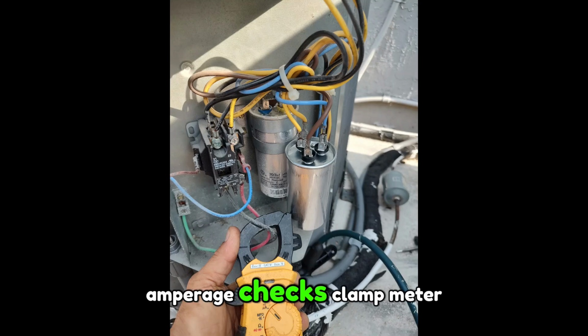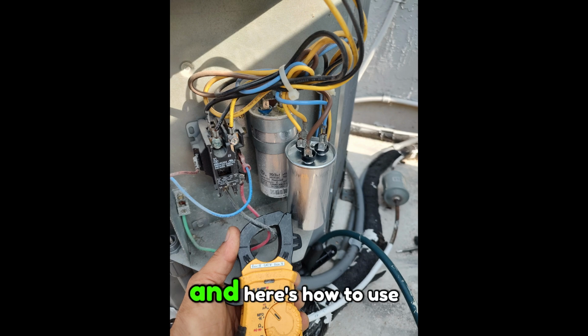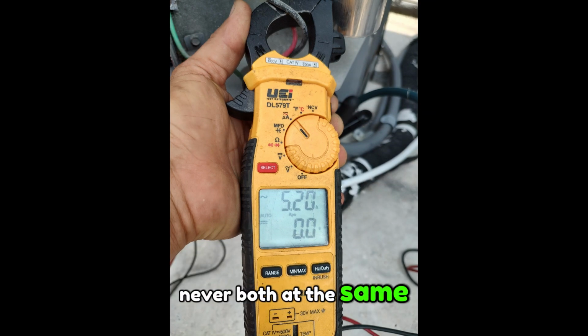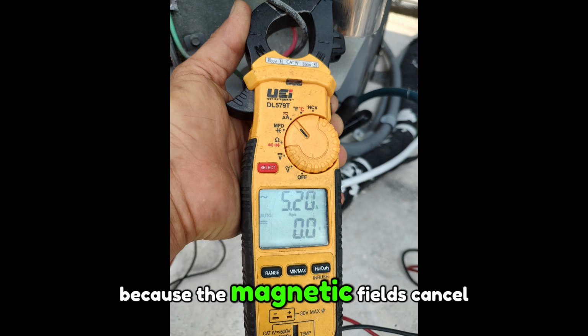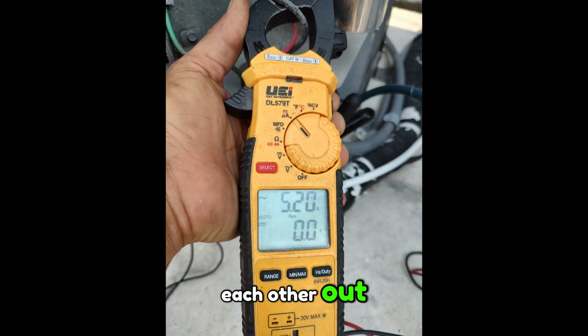Amperage checks. Clamp meter. Used to measure current, you'll need a clamp meter, and here's how to use it. Clamp around one wire only, never both at the same time. You can't measure current if you clamp the whole cable because the magnetic fields cancel each other out.